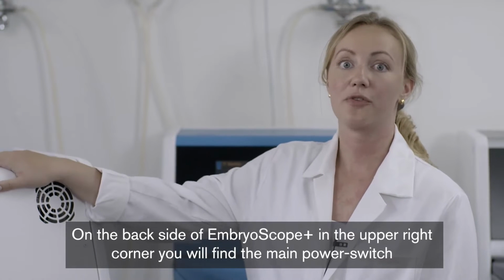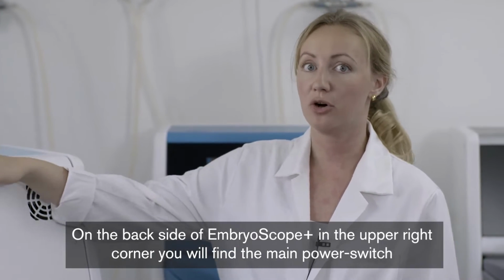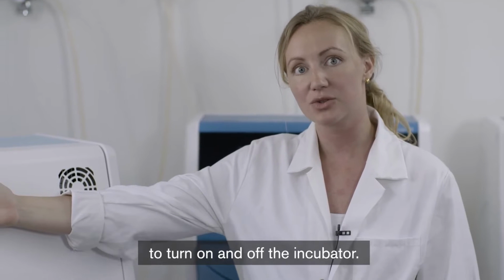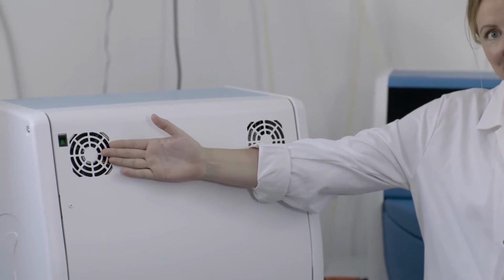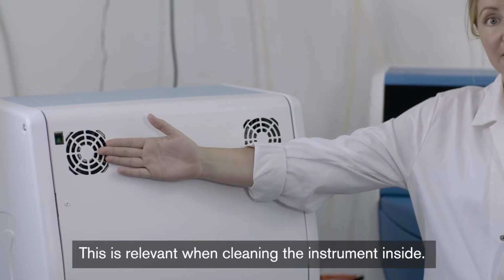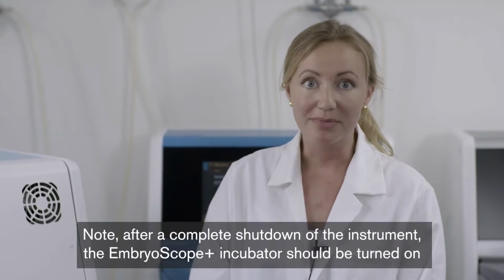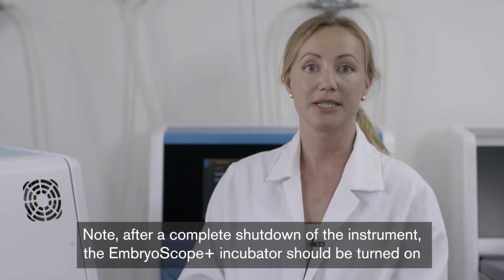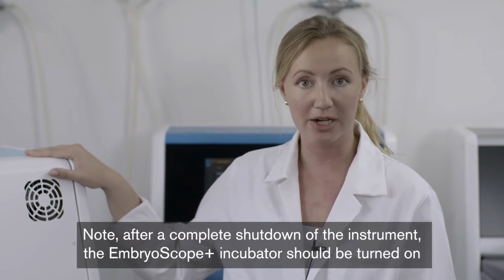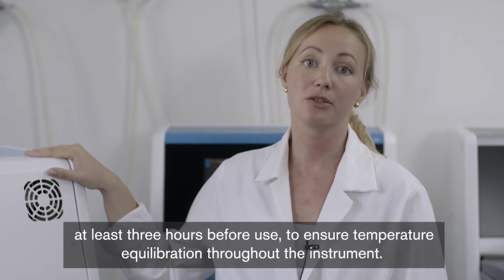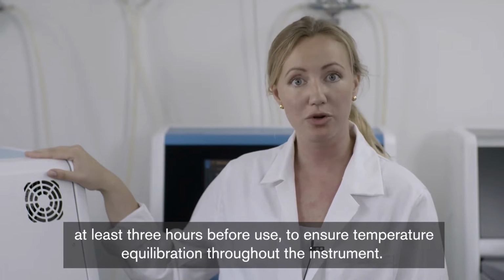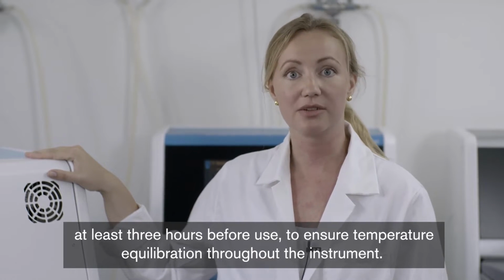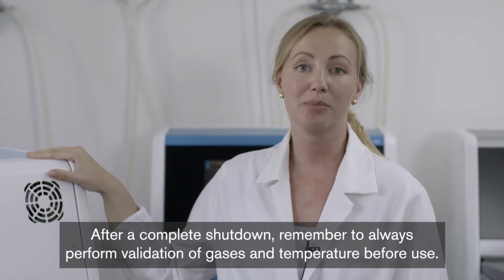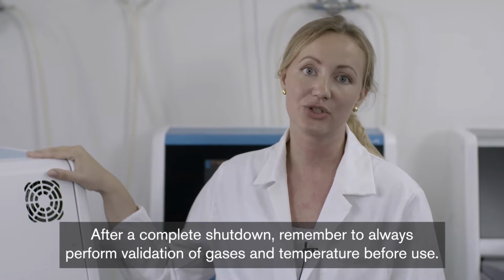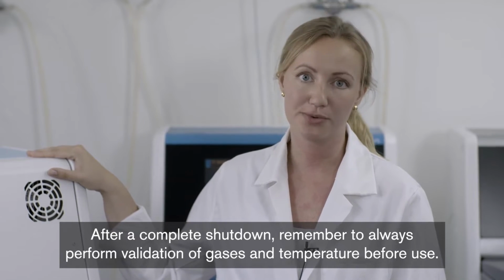On the back side of the EmbryoScope Plus, in the upper right corner, you will find the main power switch to turn the incubator on and off. This is relevant when cleaning the inside of the instrument. Note, after a complete shutdown of the instrument, the EmbryoScope Plus incubator should be turned on at least 3 hours before use to ensure temperature equilibration throughout the instrument. After a complete shutdown, remember to always perform validation of gases and temperature before use.